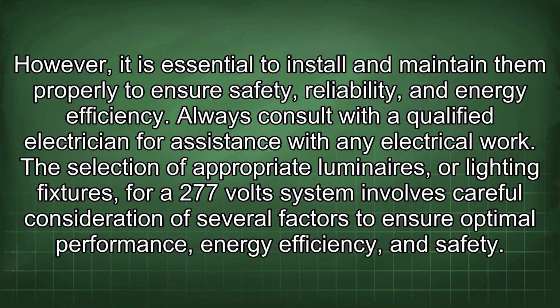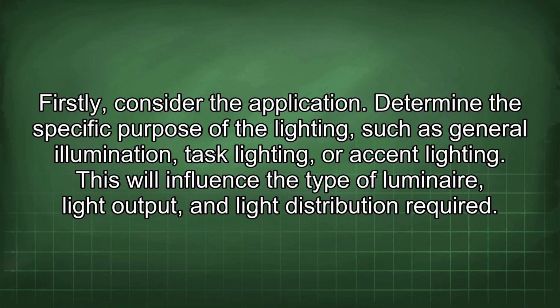The selection of appropriate luminaires or lighting fixtures for a 277-volt system involves careful consideration of several factors to ensure optimal performance, energy efficiency, and safety. Firstly, consider the application. Determine the specific purpose of the lighting, such as general illumination, task lighting, or accent lighting. This will influence the type of luminaire, light output, and light distribution required.